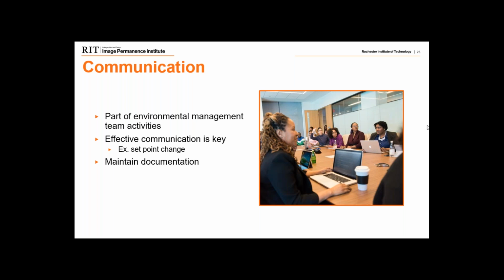Sometimes people may communicate with facilities and ask if a space can be made warmer, for example, and they may make the change, and you might see it in your data. We'll see an example of this in just a few minutes. So if you see this change and you're able to communicate effectively with facilities, you may be able to pinpoint what happened exactly and address the issue fairly quickly, rather than trying to track down if there was something else at play. You can pretty quickly attribute the effect to the cause, and that can be a real time saver.